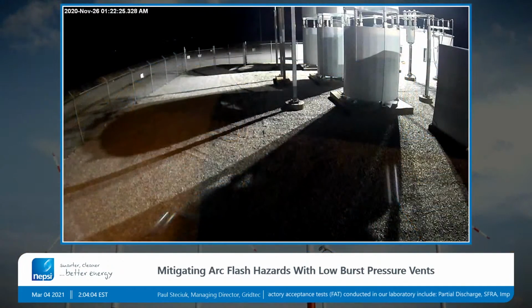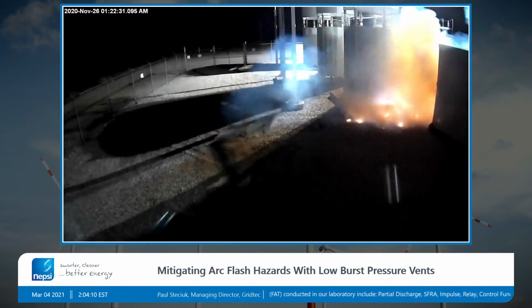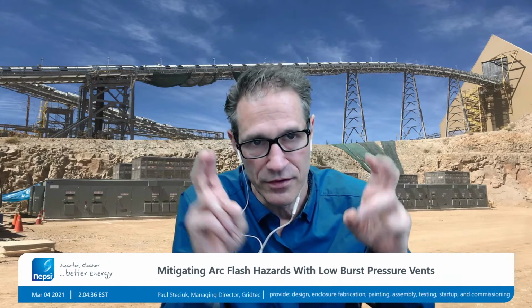So I'm going to flip over to the video that we showed last week just to give a precursor to this tech talk, just to show you arc flash events are very strong high pressure events that happen within the system. It can flip the enclosure doors right off the equipment, and if somebody is standing in front of it, they can get burned, they can get hit by the door, and it can be a pretty bad situation. So one way to mitigate arc flash hazards is to vent the high pressure inside the enclosure to a location where somebody might not be standing, and we would call this a safe zone. And we use a low pressure vent to do that.